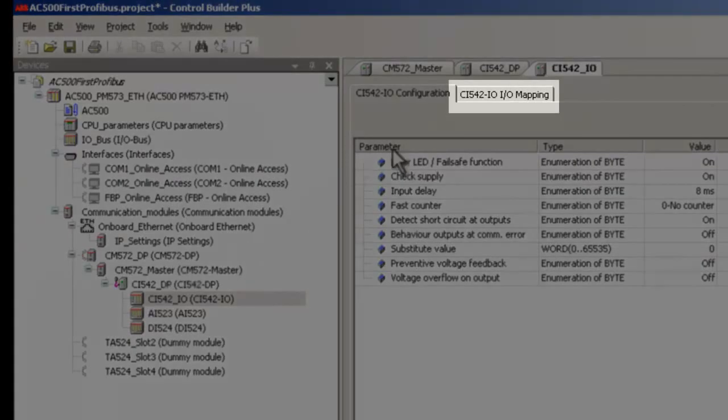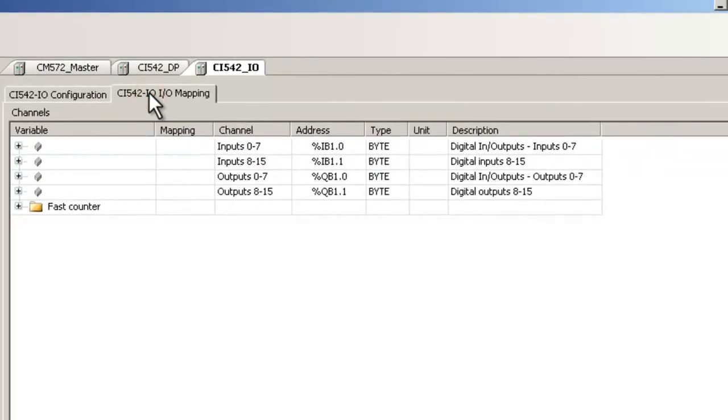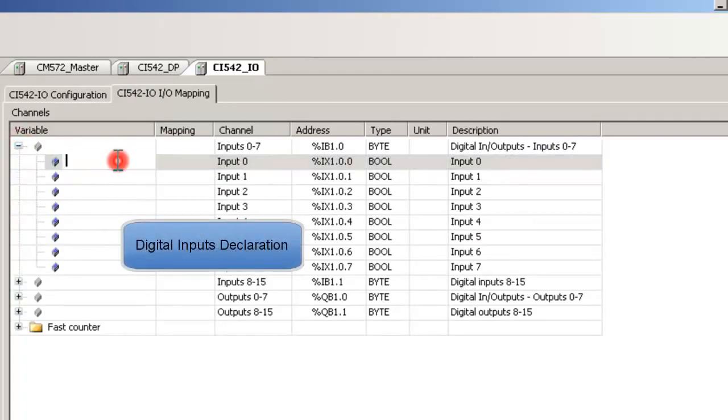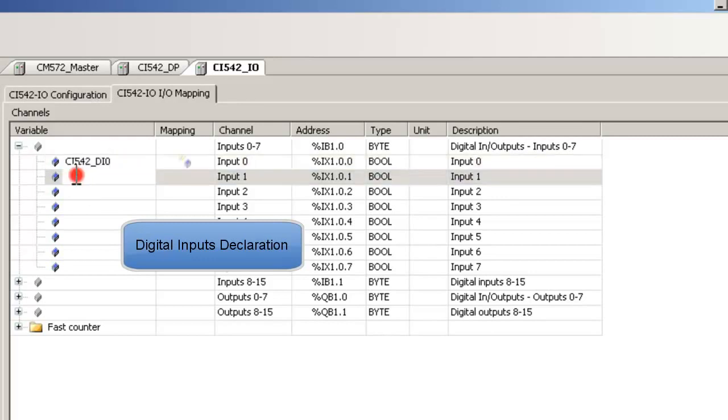Now, click on Tab CI542IO Mapping. For this module, symbols could be created byte-wise and or bit-wise. These symbols will appear in the global variable list. Here we define symbols for two digital inputs and one digital output. Just for easy recognition, we use the module name in the symbol as a prefix.